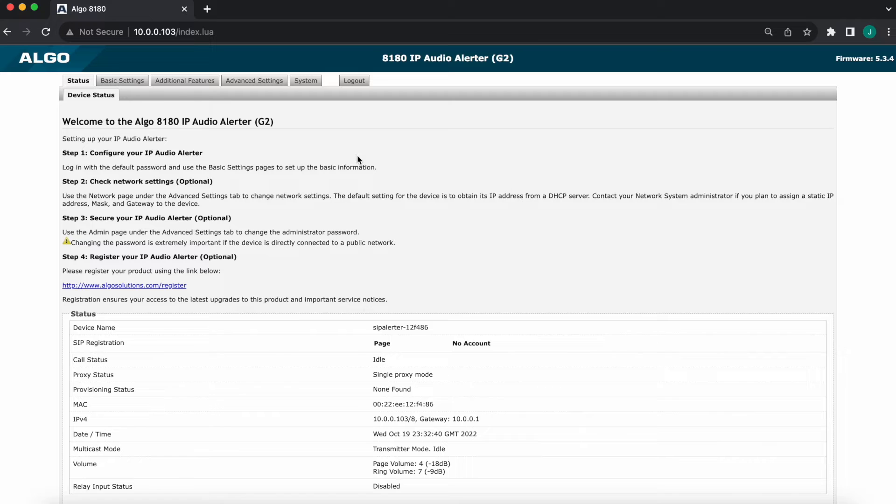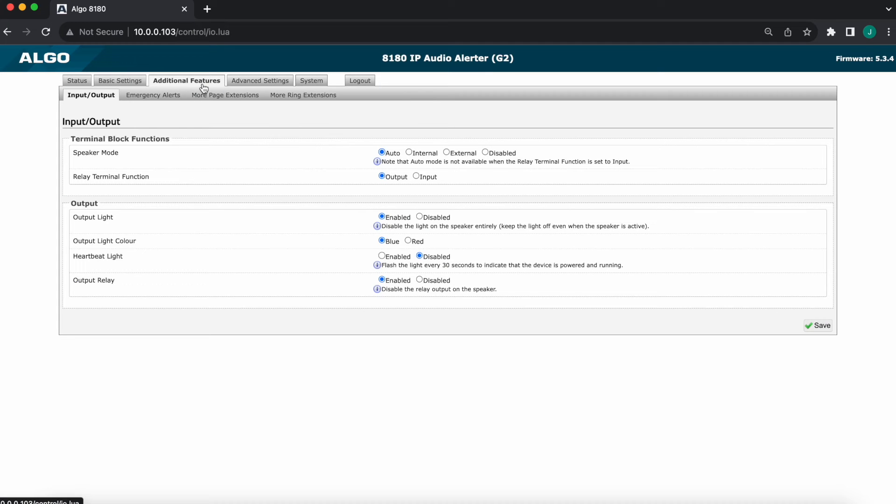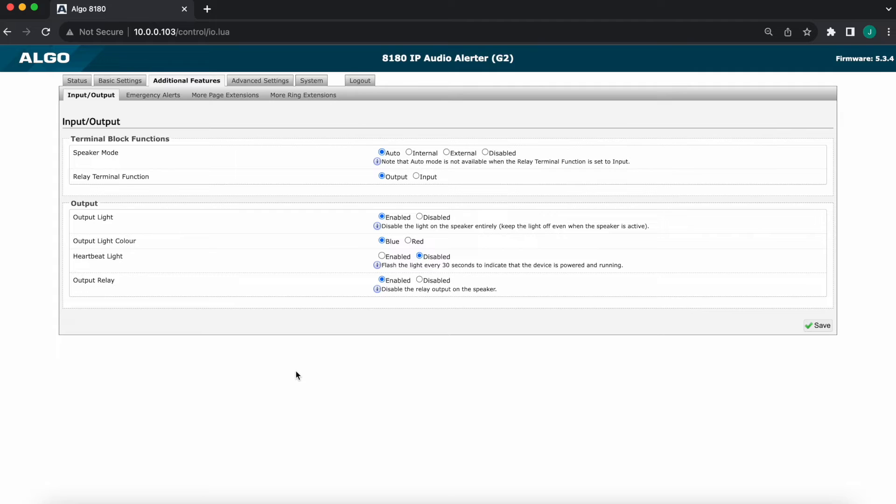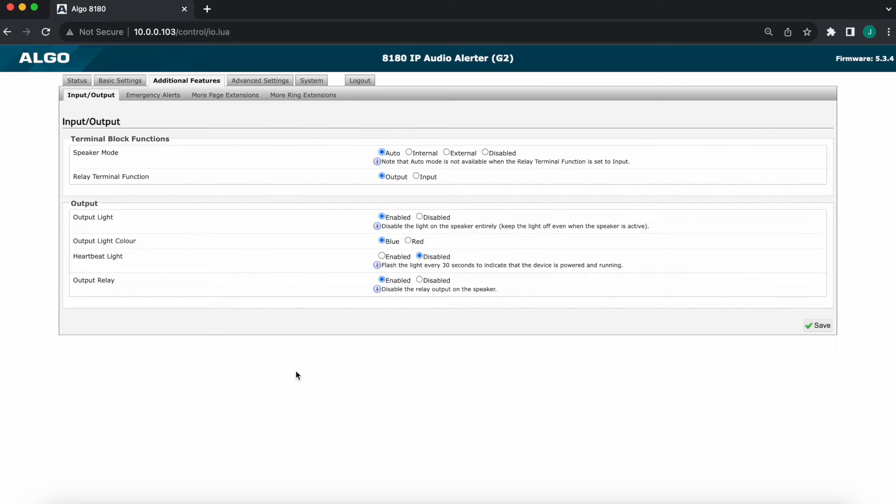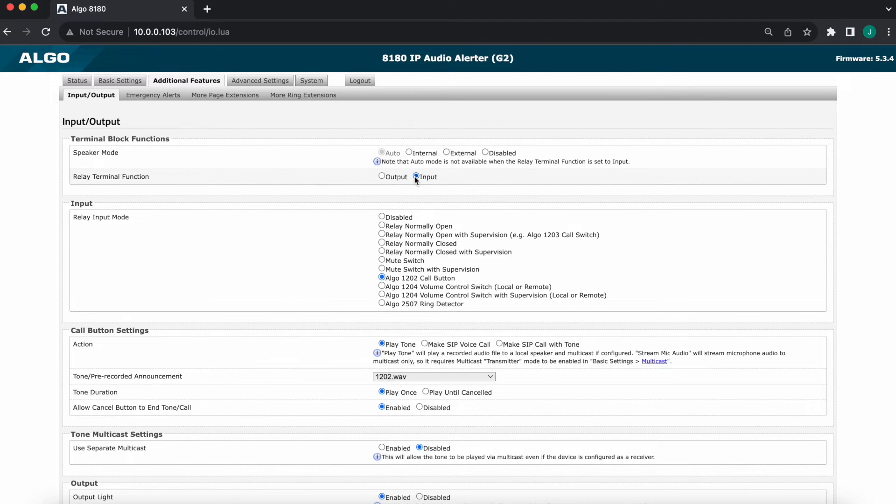One thing that we need to address is the 8180 is an exception to all the other products. This has a single relay terminal that is configurable as input or output. All the other products, no exceptions, everything else that has a relay on and is compatible with one of these two will have a relay input or output terminal. The reason why this 1202 right now is not yet illuminated is because the 8180 by default is set to relay output mode. So we'll go ahead and first thing in the web interface, as you can see, set it to input mode. Bear in mind this is, again, exclusive to the 8180.